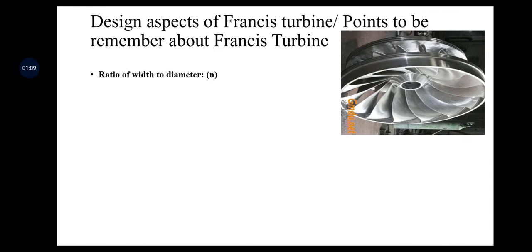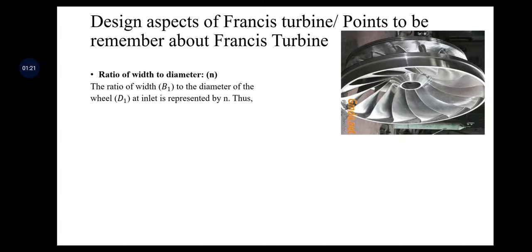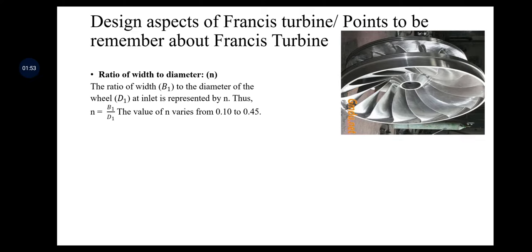The first parameter is the ratio of width to diameter, denoted by n. It is the ratio of width B1 to the inlet diameter D1. B1 represents the width at the inlet section and D1 is the inlet diameter — both related to the section through which water enters the runner through the vanes. Generally, the value of n ranges between 0.1 to 0.45.